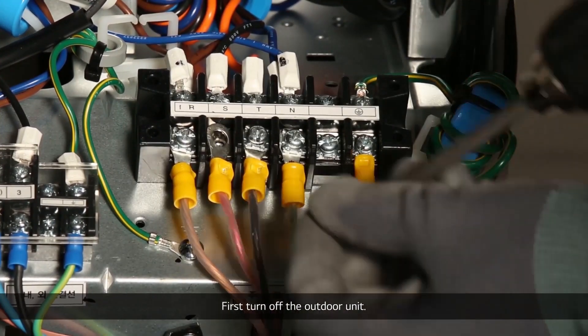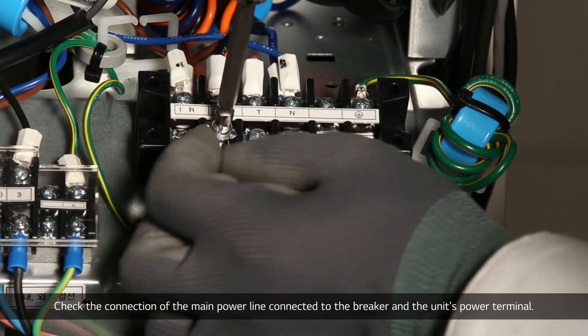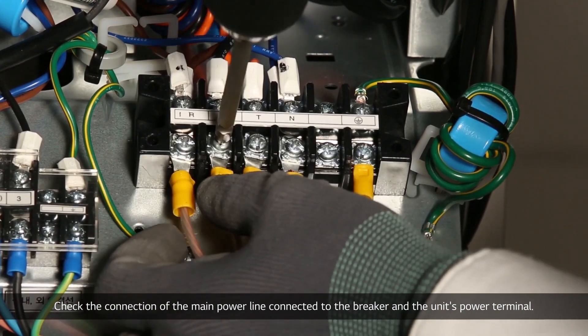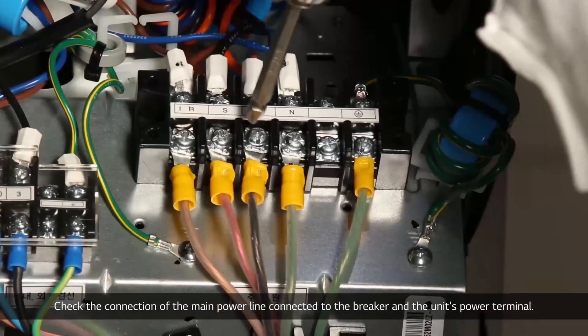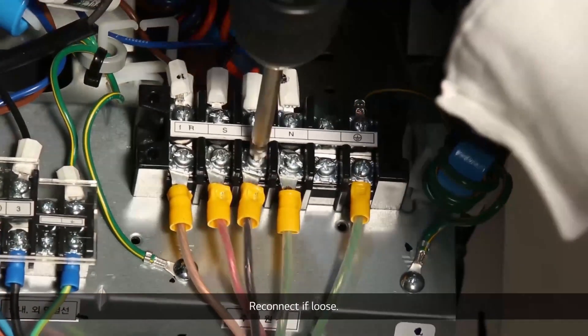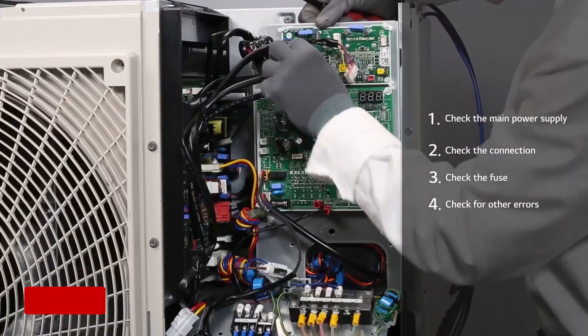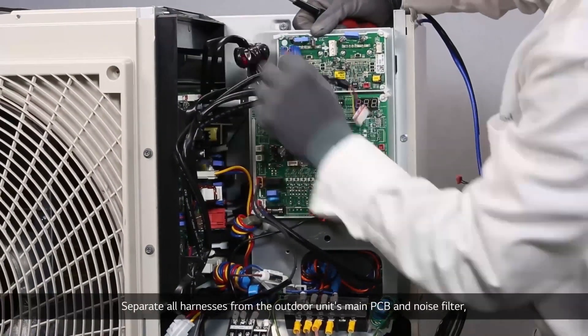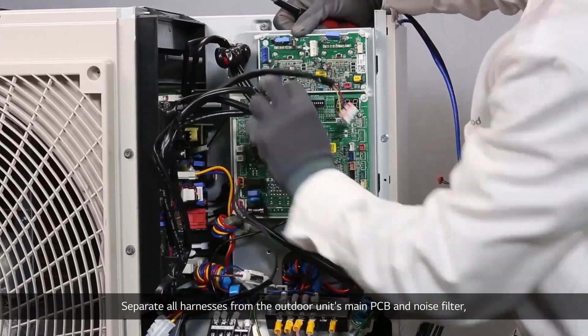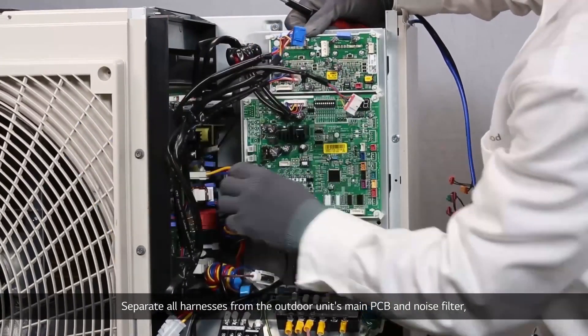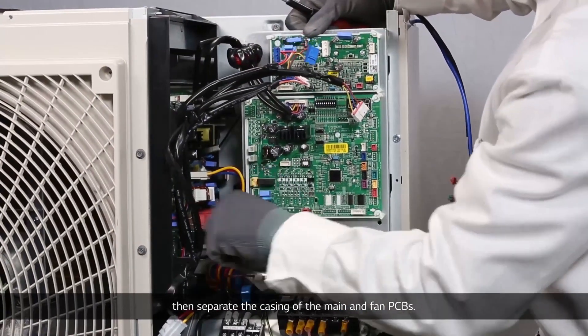First, turn off the outdoor unit. Check the connection of the main power line connected to the breaker and the unit's power terminal, reconnect if loose. Separate all harnesses from the outdoor unit's main PCB and noise filter, then separate the casing of the main and fan PCBs.